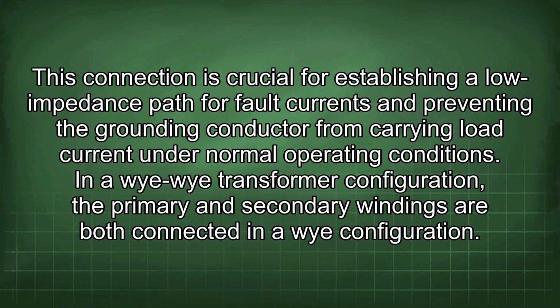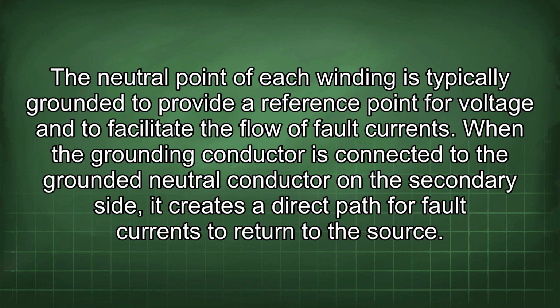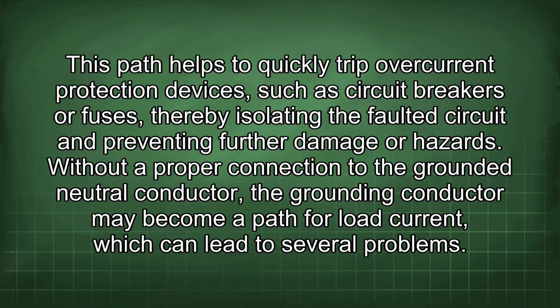In a Wye-Wye transformer configuration, the primary and secondary windings are both connected in a Y configuration. The neutral point of each winding is typically grounded to provide a reference point for voltage and to facilitate the flow of fault currents. When the grounding conductor is connected to the grounded neutral conductor on the secondary side, it creates a direct path for fault currents to return to the source. This path helps to quickly trip overcurrent protection devices such as circuit breakers or fuses, thereby isolating the faulted circuit and preventing further damage or hazards.